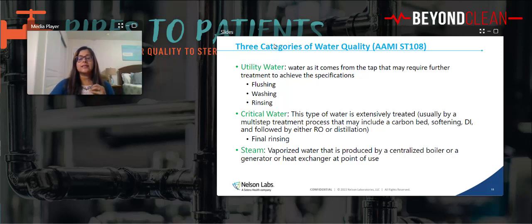Now, critical water is water from utility that has been further processed down the road through filters, through processes of water softeners. I'm sure you guys have heard of water softeners, reverse osmosis, test membranes, things like that. And that is used for final rinsing for cleaning validation. And we use critical water after HLD, high-level disinfection processes, right? Because high-level disinfection process is the last process for the validation and also last process before it sees the patient.